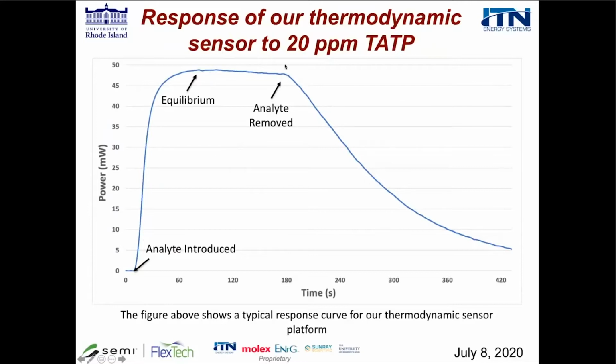We would not be using this whole protocol in a real application. We would be using some kind of initial response and then essentially have a duty cycle to turn the sensors on and off, so we wouldn't have to wait so long to see if the analyte is present.